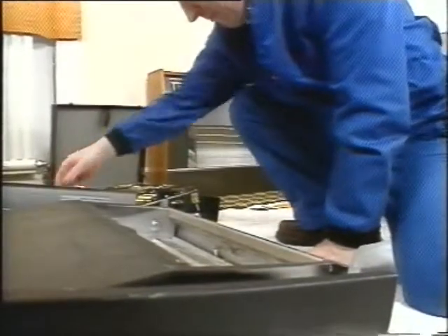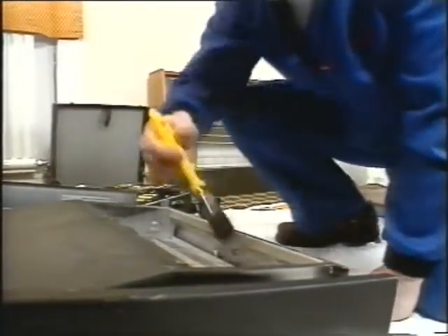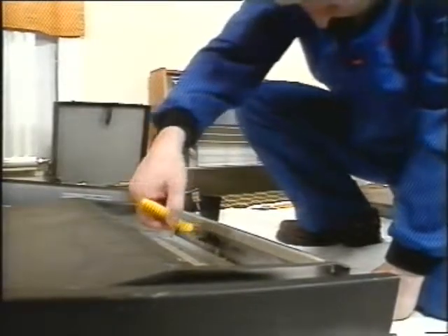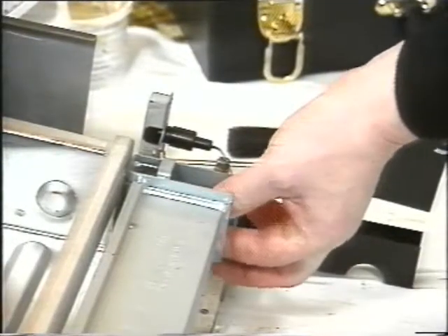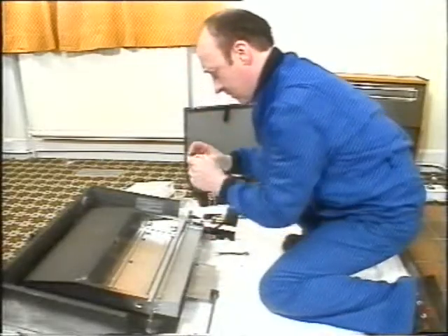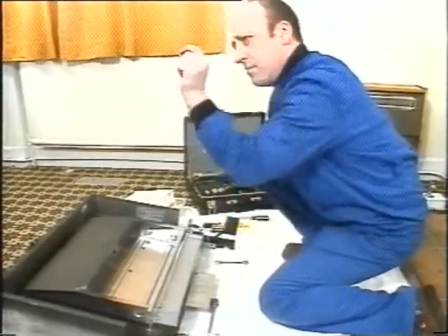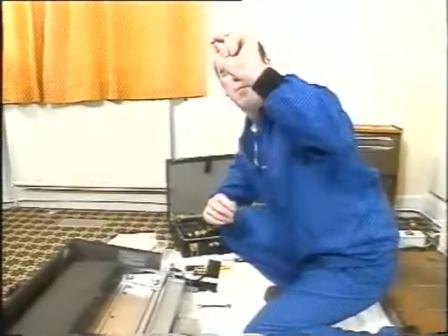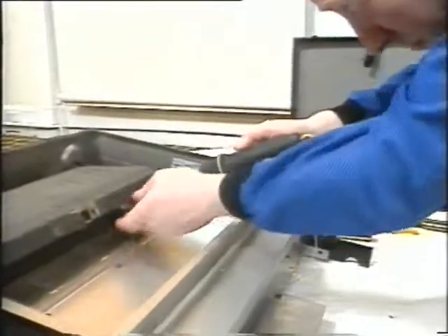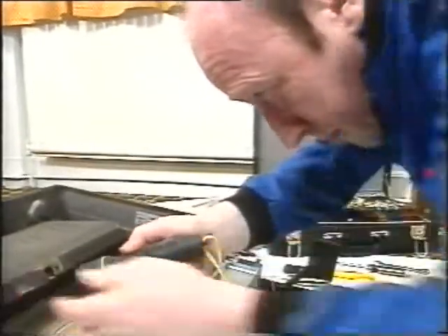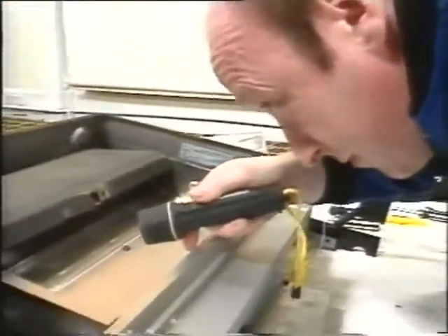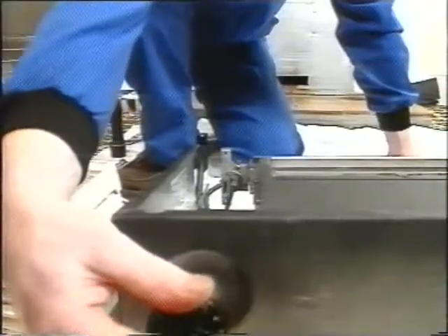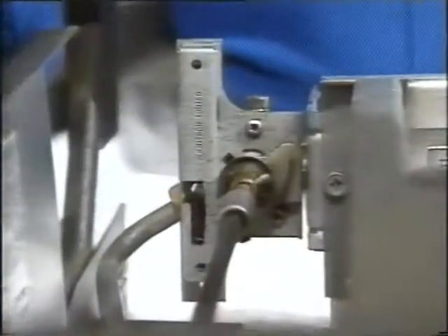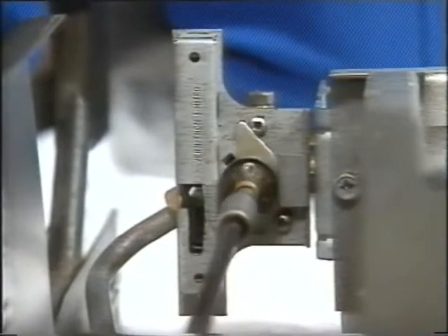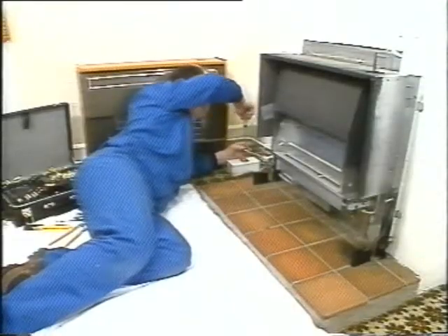When you've taken off the case, you can remove the radiants. Next, clean all the dirt and lint from the grills and burner. There may be one or more injectors. Check and clean them. Make sure that the heat exchanger is not corroded and that the flueways are clear. Grease the control tap if it needs it. Then reconnect the fire and test the gas installation for soundness.